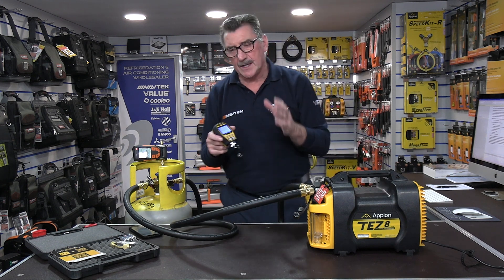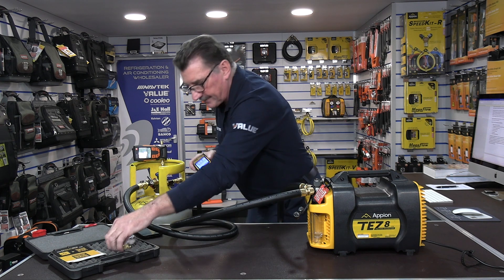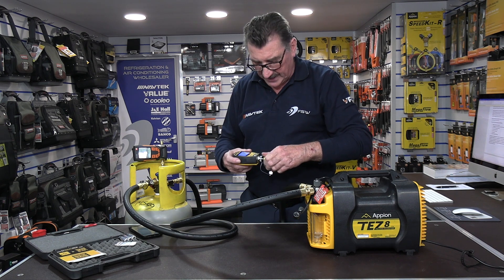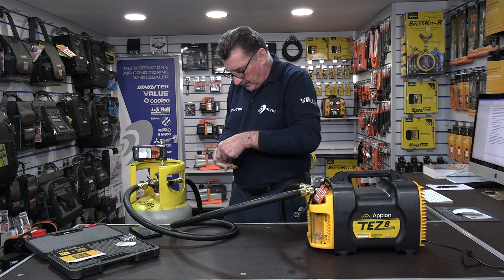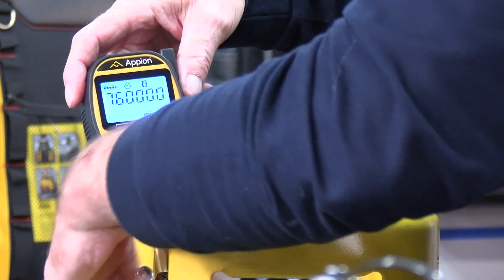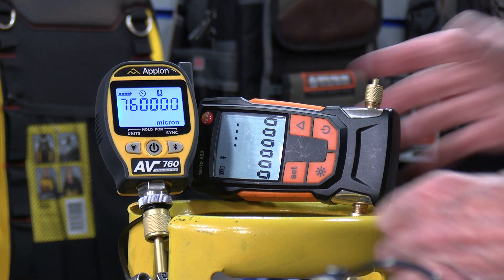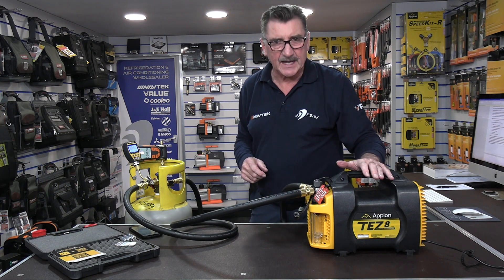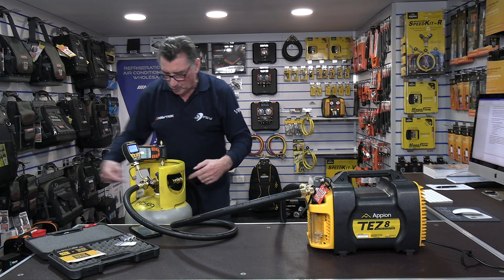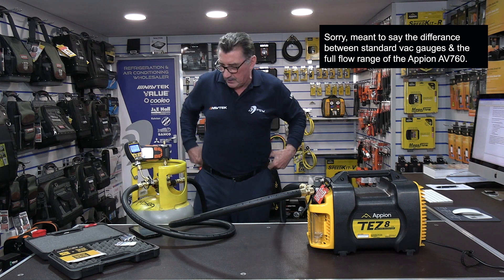The key thing I want to show you is what Appion mean when they say full range. To do that, I need to connect the vacuum gauge adapter. I'll use the one that comes with it because it's lovely quality Appion kit — we'll screw this on. I've got this in close-up on the camera. I'm going to switch on the TEZ8 vacuum pump. I've got two high-flow hoses, one going to the liquid valve and one going to the vapor valve, and two core tools on there to show you the difference with high flow. The Appion is already reading because it reads from atmospheric — you can see it there.